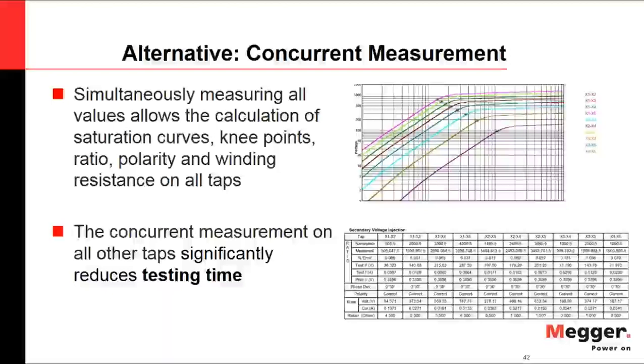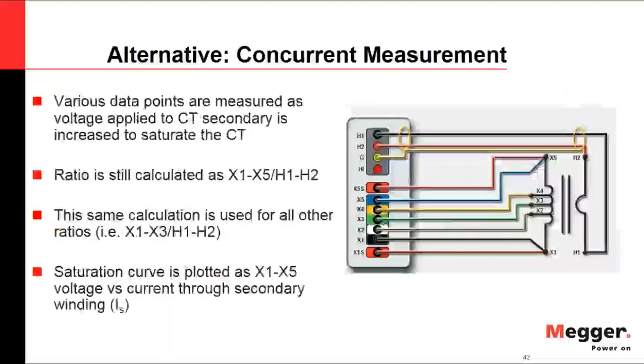During concurrent measurement, voltages are applied to the CT secondary and increased to saturate the CT. The ratio is calculated as the ratio of voltages between X1-X5 and H1-H2, and inter-winding ratios are calculated based on the voltage relationships between primary and secondary. The saturation curve is plotted between X1 and X5, and all inter-winding saturation curves are calculated and plotted simultaneously.